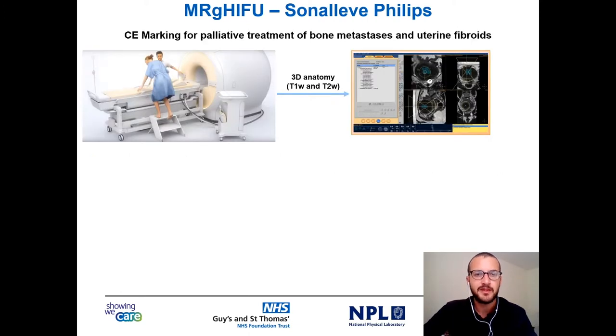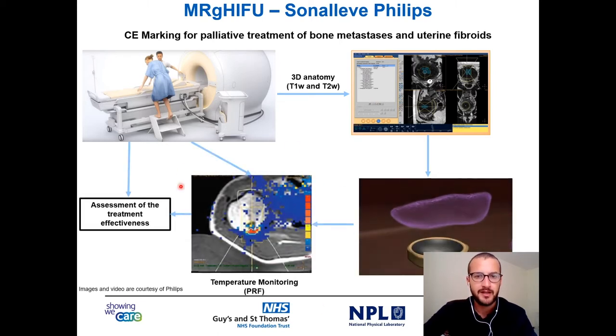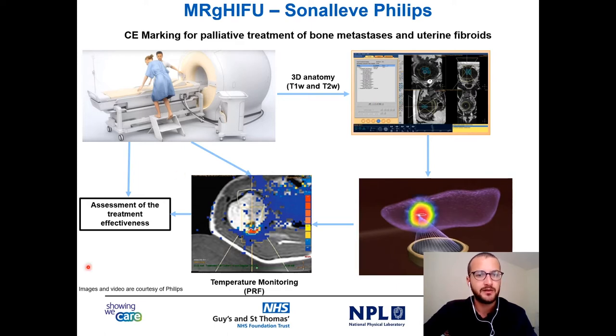At St. Thomas Hospital, we have a Sonalleve, which is cleared for treatment of bone metastasis and uterine fibroids. The patient is positioned into the MRI scanner and an anatomical image is taken for treatment planning. The HIFU transducer delivers high-intensity focused ultrasound, while MRI thermometry allows real-time monitoring of the temperature rise. Later on, you can take another image to assess the treatment effectiveness.